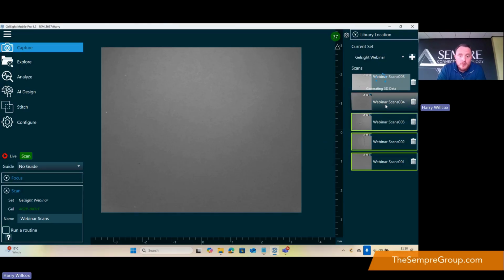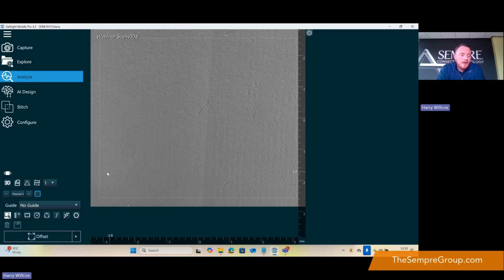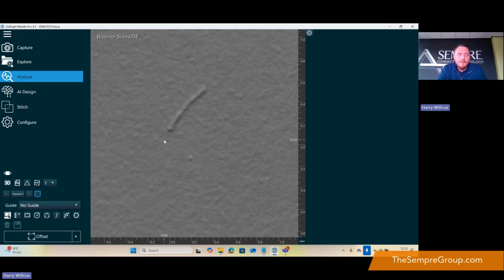For the first scan that I've measured, we start to look to see whether I see this mismatch. This is a really good example to show the difference in the orientation of the light as to what visually you can see. As I'm clicking this button, I'm looking at the different channels. When we say channel, that's the different LED that is used to take our image. It's quite a good thing that there's some debris on the surface, because it helps us understand what's happening with the light. Currently, the light is coming from what I would define as a Z positive, or for some people, depending on the left-hand rule, it might be your Y positive direction.